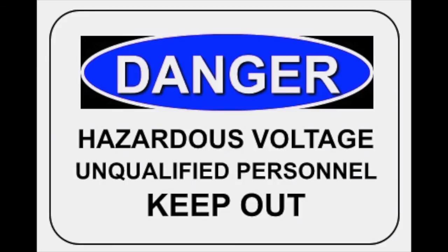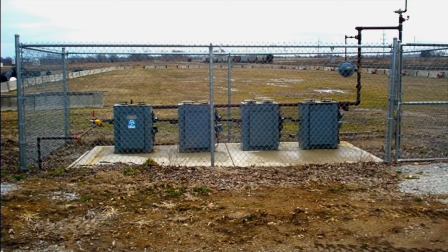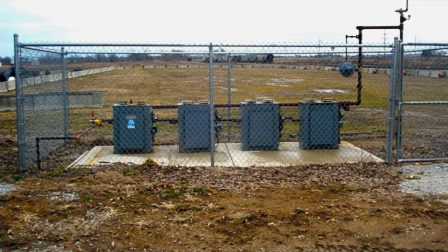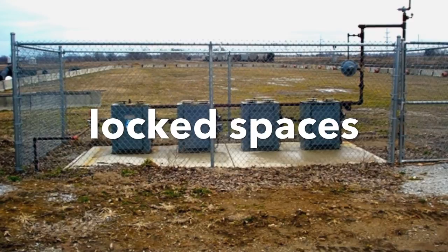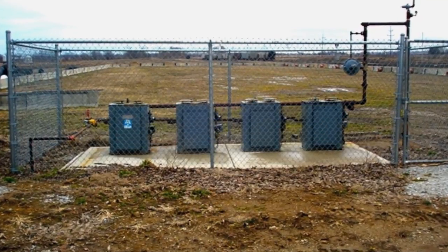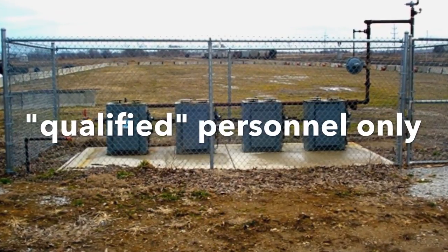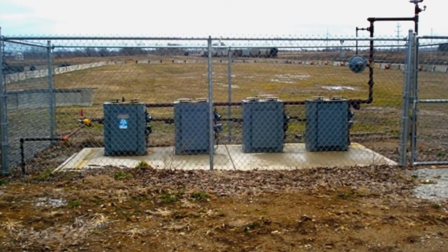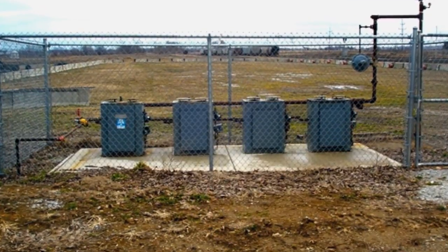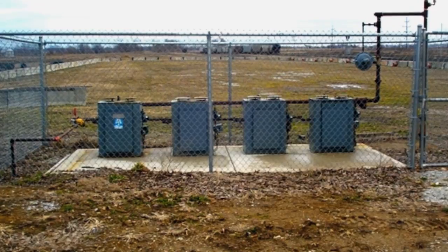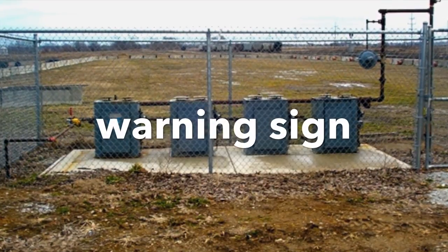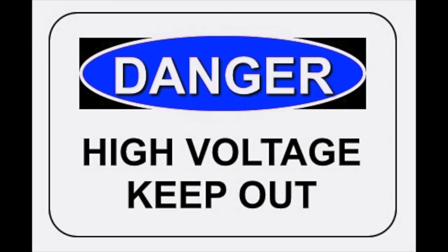Here we see an example of a danger tag for unqualified persons. Electrical installations in a vault, a room, a closet, or surrounded by a wall, screen, or fence that is locked is considered accessible to only qualified persons. Entrances to all buildings, rooms, or enclosures that contain over 600 volts will be kept locked, and warning signs must be posted stating danger, high voltage, keep out.